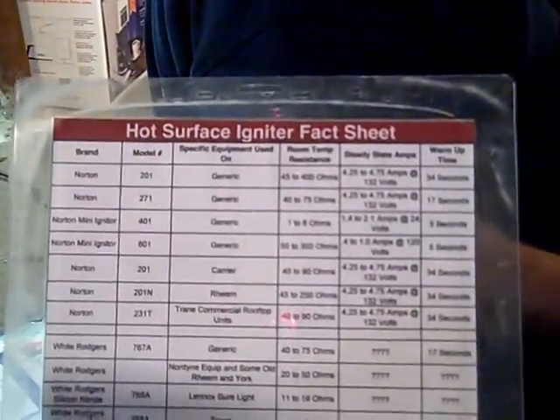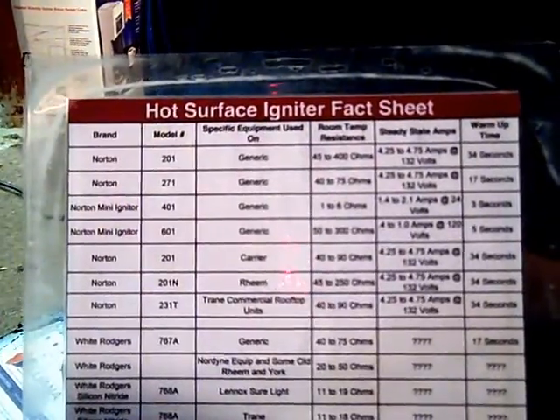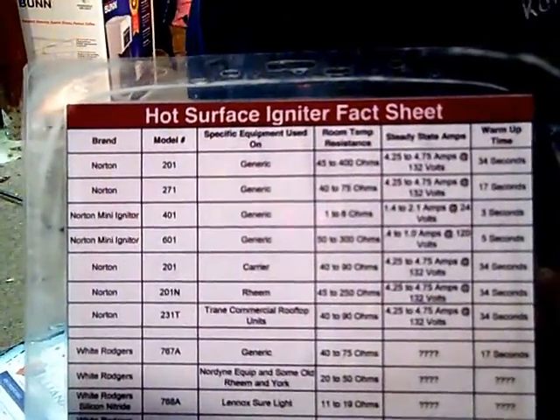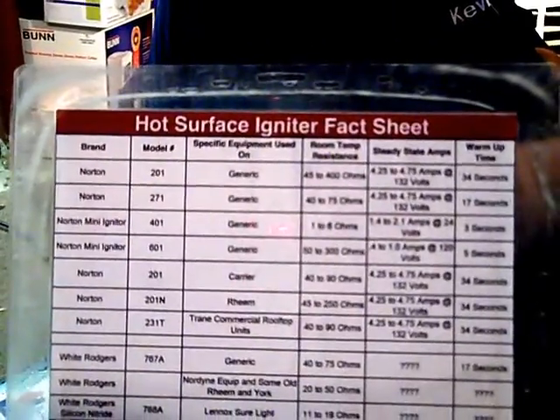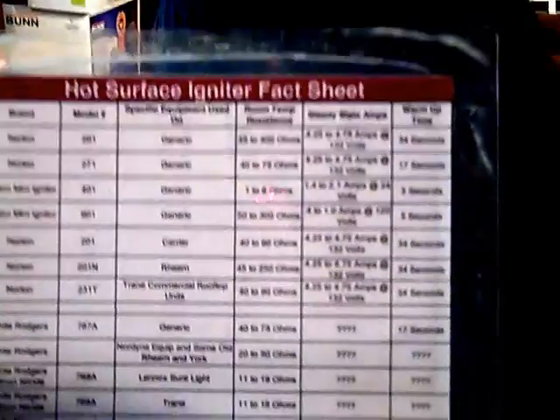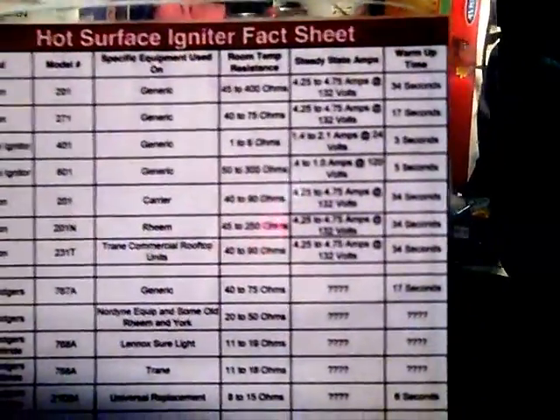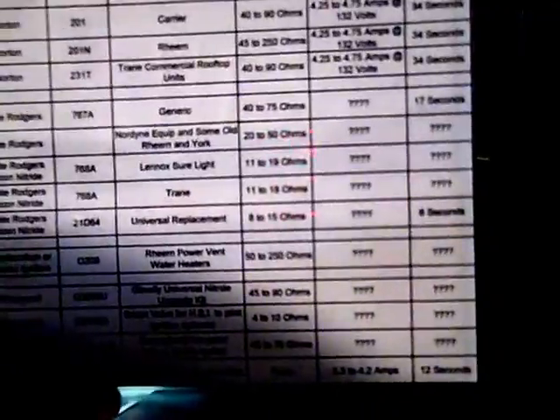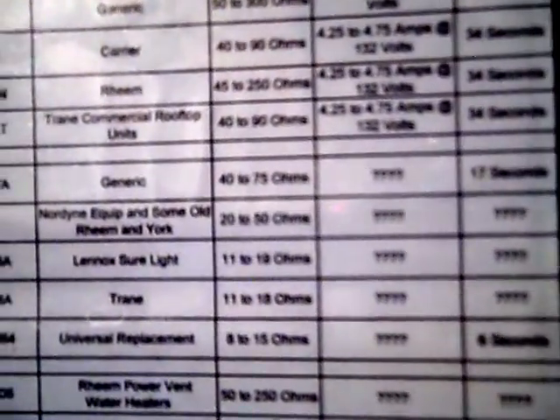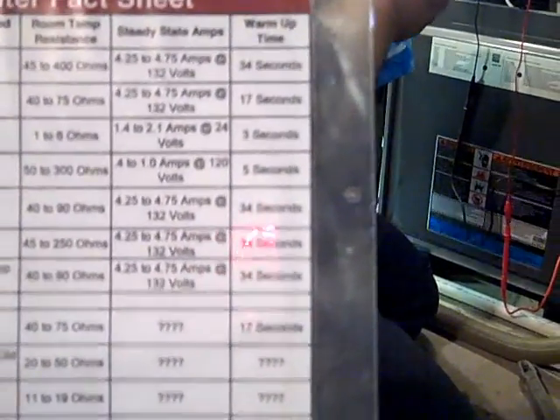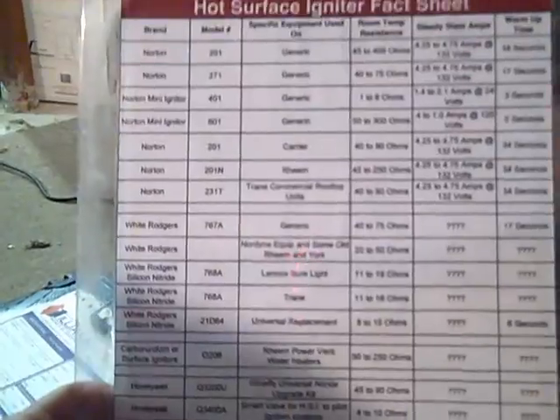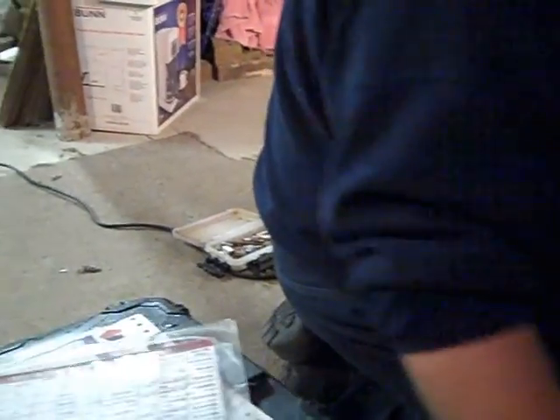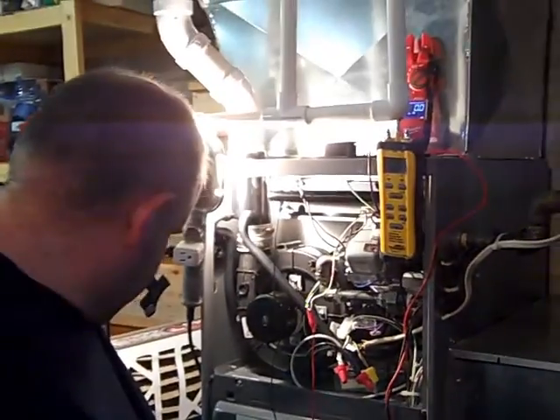He's got this sheet for hot surface igniters. It tells you what the model of the hot surface igniter is, which specific equipment, if any, it works on, and what the room temperature resistance, the ohms, should read on this. This way, when you're doing a service call, particularly just a tune-up, you specifically know if the hot surface igniter is good, if it's weak, if you should recommend a new one. It tells you about the warm-up time. You have to keep information like this around. The reality is you cannot memorize everything, particularly because there are so many models around nowadays.